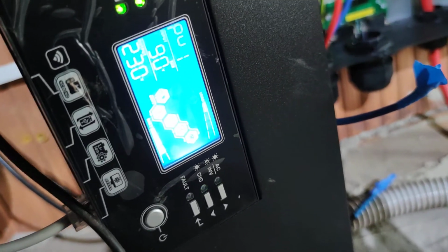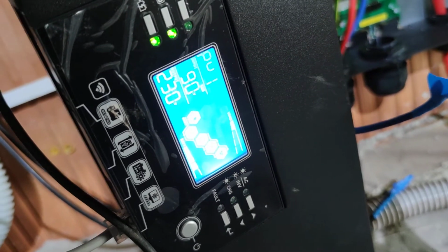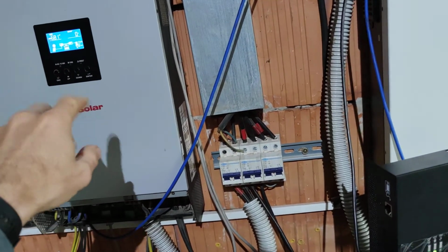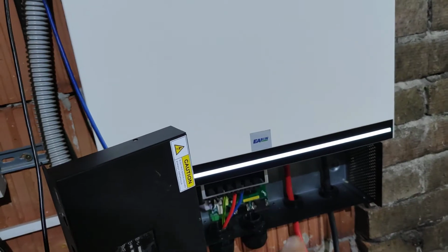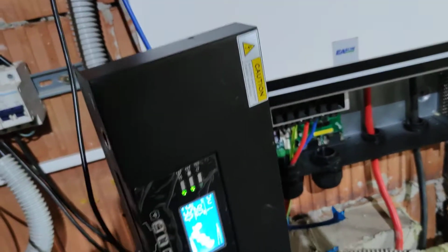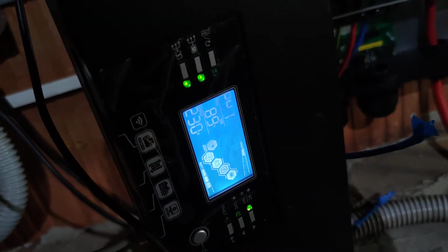Okay, the inverter has another issue, and that is that the MPPT tracking doesn't work properly. So let me show you an example. I have two inverters, in fact, installed, one side by side. This one is the MPP Solar 5 kW one, and this one is obviously the new one, the 8 kW EASUN inverter. They have an equal amount of panels installed, so 3.6 kW, 3.6 kW.